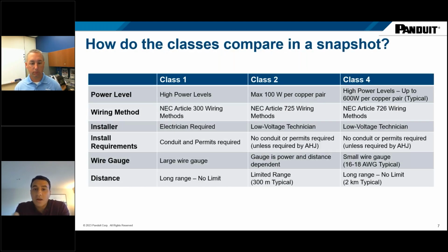Just in a quick snapshot now, how does Class 4 compare to 1 and 2? So power levels for Class 1, very high power levels. Class 2, limited to 100 watts per copper pair. Class 4, there is no limit on the power level. However, you'll see very typical 600 watts per copper pair. We talked about the installation requirements. So again, given that Class 2 and 4 are considered safe from an installation perspective, you can have a low voltage contractor install them. You do not have to run them in conduit, but that's again very specific to local jurisdiction rules.